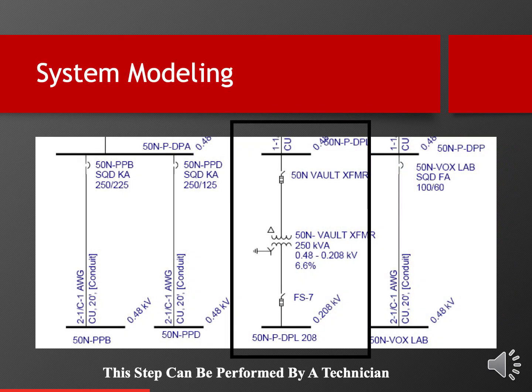What you see in front of you is just a snippet of the low voltage part of an arc flash risk assessment study. Now again, this is only there to give you an example. And what you're seeing here is a 250 kVA transformer installation that has a high voltage, high side fuse, which is labeled 50N Vault transformer. The transformer itself, and then underneath is the low voltage or the 208 volt fuse, which in this case is labeled FS-7. Now, what you need to understand about the system modeling component is that we normally only include things in the system model that impact the incident energy calculations. So we don't normally put in things like solid blade disconnects or devices that don't interrupt current flow because they have no bearing on the incident energy. So a system model diagram is useful, but it is not the same as an electrical schematic diagram you would use for troubleshooting. So just kind of keep that in mind, those of you who are working people.